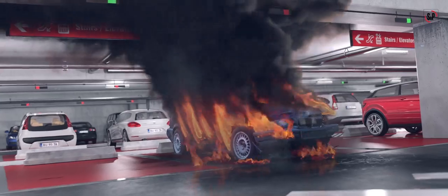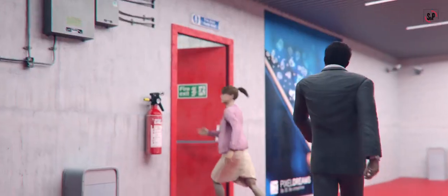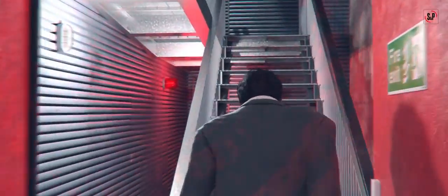Because, in the event of a fire emergency, hot smoke rises and sensors operate alarms and fire-related extract fans to assist safe evacuation of occupants, via stairs which can be pressurized by fans to resist smoke entry and assist safe exit. Extract fans exhaust this hot smoke to atmosphere.